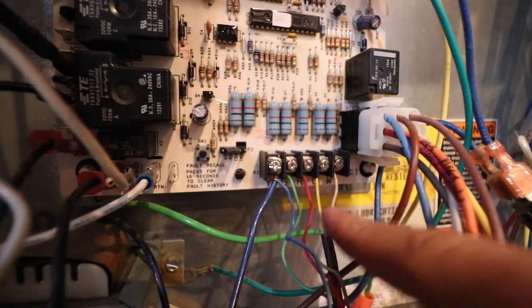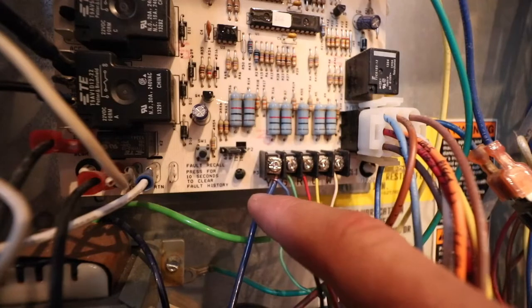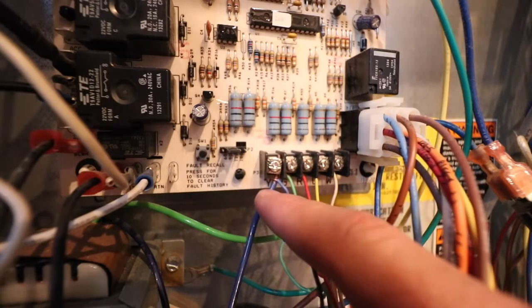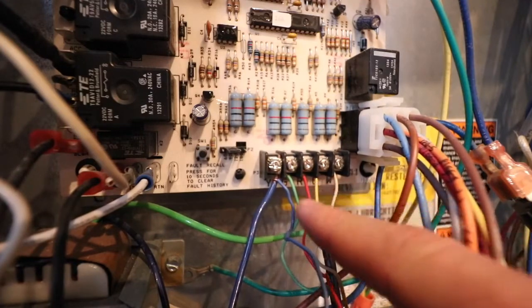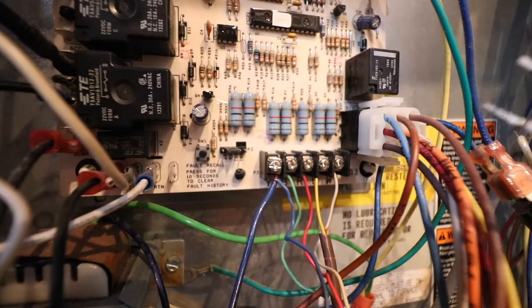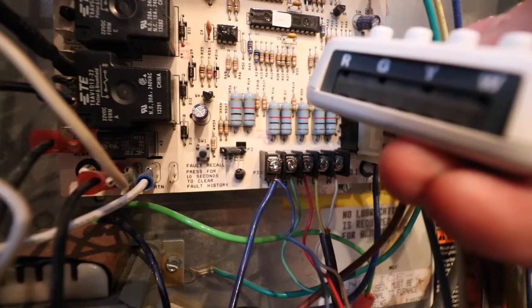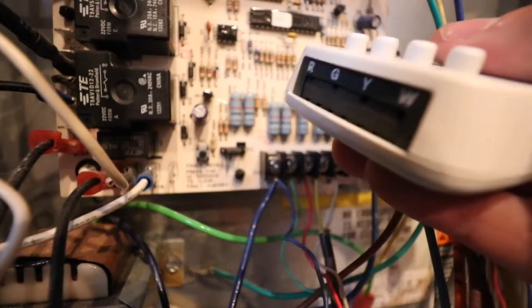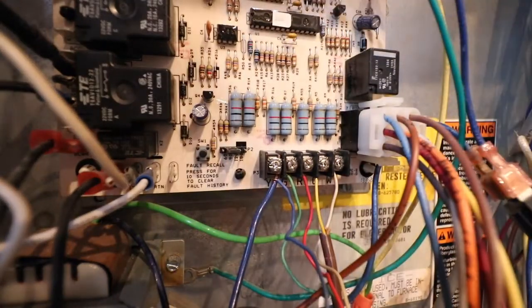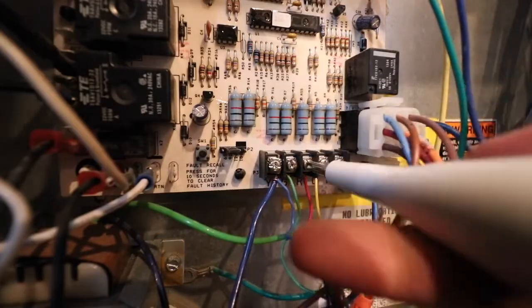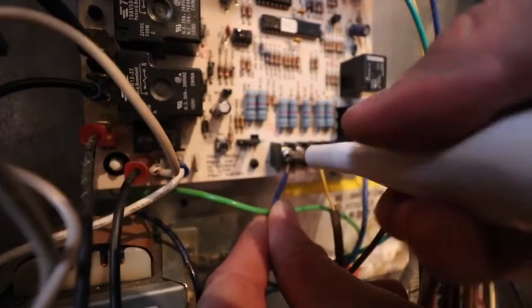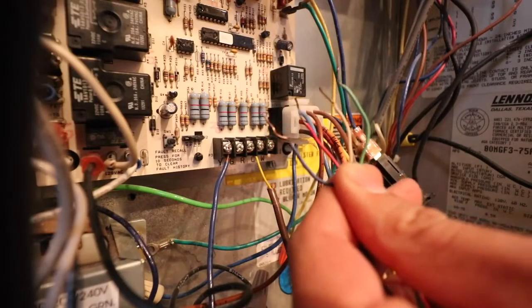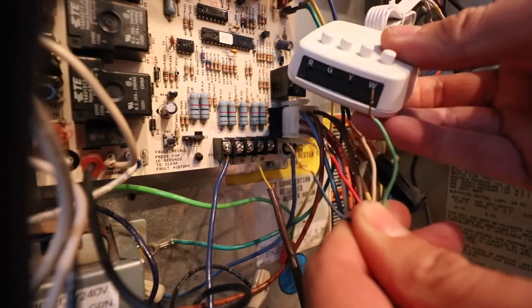Now these other 2 wires that we have, this yellow wire and this larger blue wire, they're going to need to stay connected because those are for our air conditioner compressor. So they will remain on those terminals while we install the new common wire adapter and put the wires coming from the thermostat into the bottom of the common wire adapter. So let's go ahead and remove the wires, and we're going to plug them into this common wire adapter, and we're going to wire up the common wire adapter. Now we've got our 4 wires loose here, and we're going to plug them into the appropriate terminals on the common wire adapter.